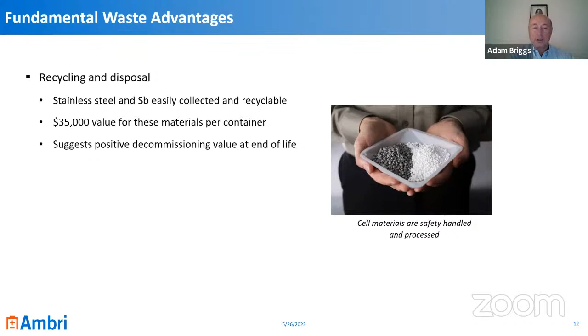I've mentioned that these batteries are quite safe. This is testing recently and successfully completed with Underwriters Laboratory at the cell level. UL 1973 is the typical but difficult safety certification for rechargeable batteries. Lithium-ion batteries, for example, will pass this test, but only if they are in a module which has safety electronics around those cells. Essentially, if you short circuit a lithium module, a switch will open up, stopping the current through that cell.